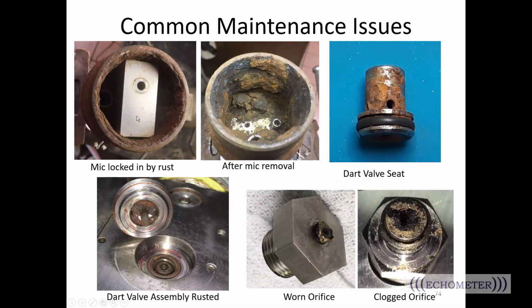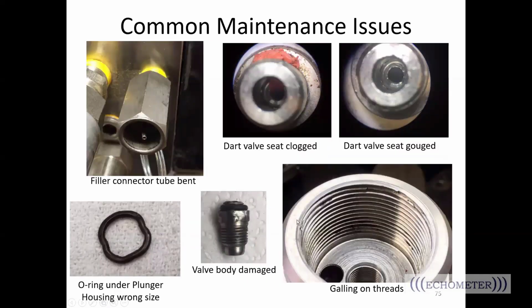All right, some common maintenance issues. So here is the microphone was locked in by rust, and so this was after the microphone was removed. And this might be the one that Edwin was talking about. Yep. Here's the dart valve seat. All right, you can see that's in bad condition. Here, the dart valve assembly is rusted. Here we see a worn orifice and a clogged orifice. All right, so these are all parts that would need to be replaced. The filler connector tube is bent here. The dart valve seat in this picture is clogged, right? You can see a bunch of gunk inside there. Here we have another dart valve seat that's gouged.